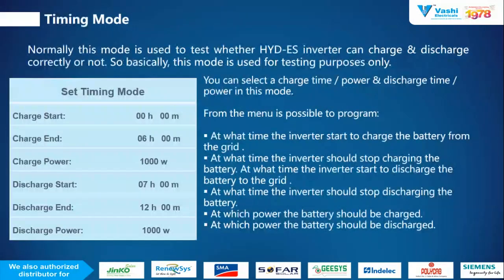Now the third is the timing mode. Normally this mode is used to test whether the hybrid inverter can charge or discharge correctly or not. So this is one kind of testing mode through which you can easily check whether the inverter is working fine or not, and whether it will charge your battery correctly. So this mode is for testing purposes only.